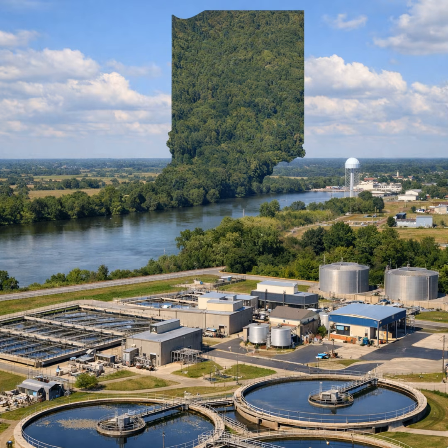Tapered aeration. Tapered aeration affects only the arrangement of the aeration devices in the aeration tank. In tapered aeration, the diffusers or aeration devices are spaced closer together at the head end of the tank to match the oxygen demand. So it's just more aeration devices, closer at the head end of the tank, so they can match the oxygen demand that's in the tank.